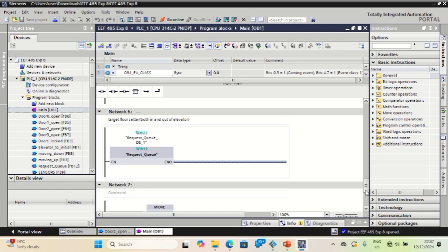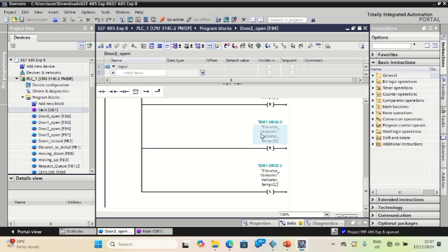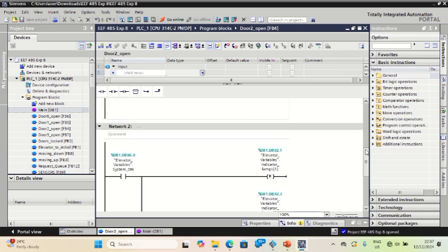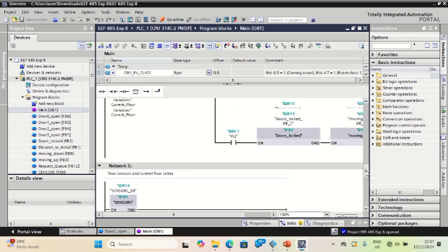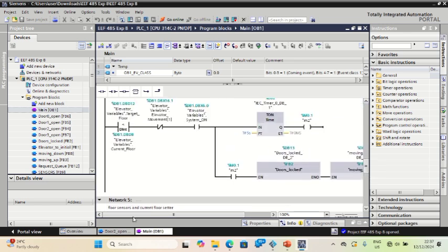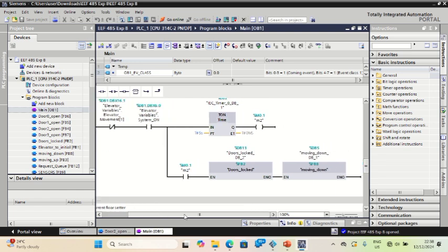Now if I want to call back this whole set of functions, suppose I want to change a single variable, say we're at floor 1, or floor 0, and all the rest will be the same, or I want to use this exact set of ladder network, I need to copy all of this and put it again in another rung or in the same rung. So you see it gets a little bit too cumbersome. That's why the aim of function blocks is just to ease the code, to help condense the amount of ladder networks that you use otherwise.